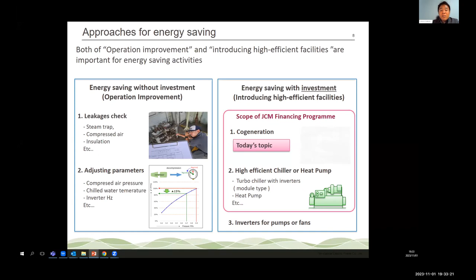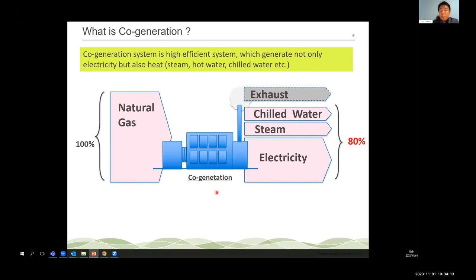Secondly, I would like to explain about cogeneration. Cogeneration uses gas engines and auxiliary units; the facility input is natural gas, and it can generate electricity. But aside from electricity, we can use the exhaust gas for steam and chilled water. Usually when we use it only for electricity, the generation efficiency is only 40%. But if we use electricity, steam, and chilled water together, the total efficiency gets to be 80%. It is very high efficiency, and it can reduce CO2 so much.